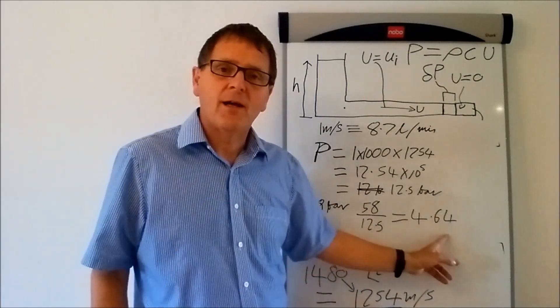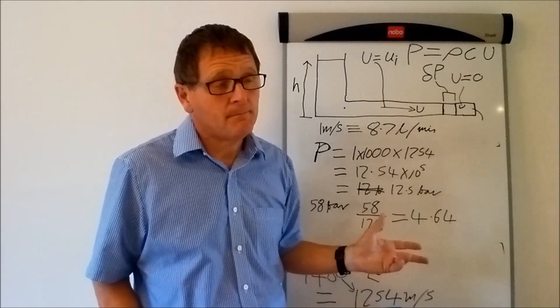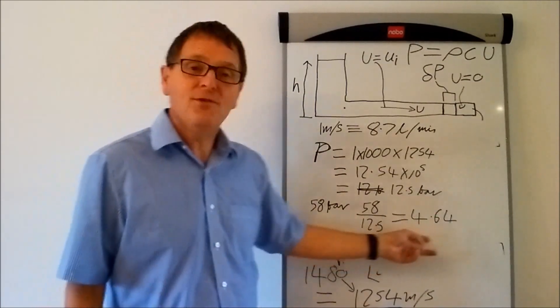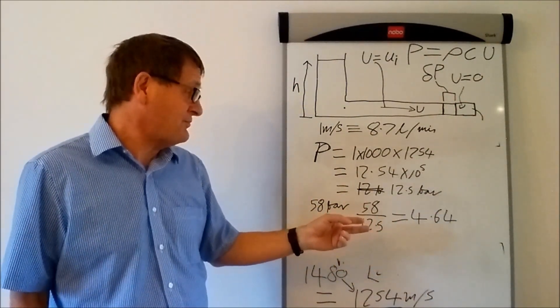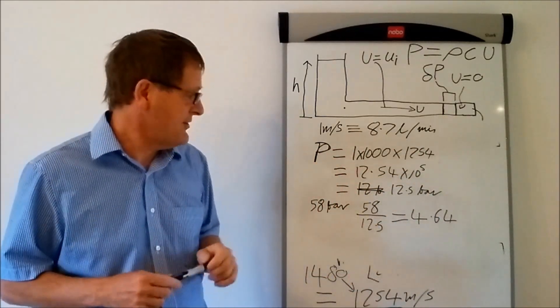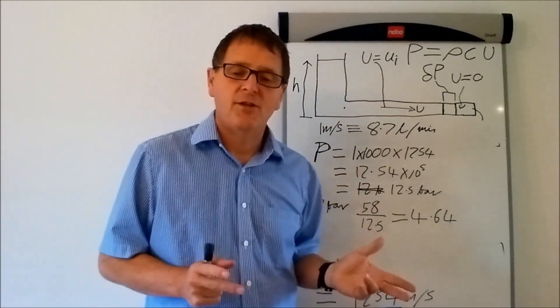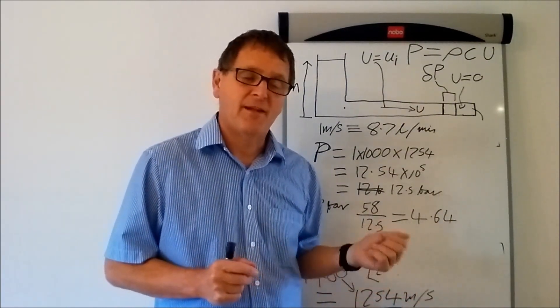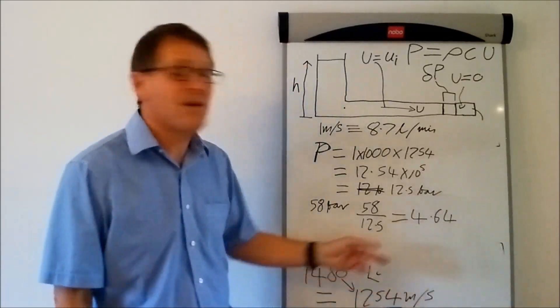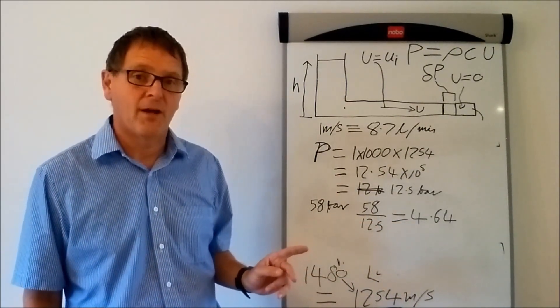I should also point out that this is a copper pipe. Nowadays in domestic situations they're going more towards plastic pipes. The pressure rating is probably less — I'll leave you to do those calculations — but you'll also find that the wave speed will be a lot lower, so there's probably a balance there. In a domestic situation with a tap, there's usually some mechanism at the back of the sink for adjusting the flow. That's what a good plumber would do — he would set it up so that you don't have too excessive a velocity, and therefore you're not going to exceed the pipeline pressure.